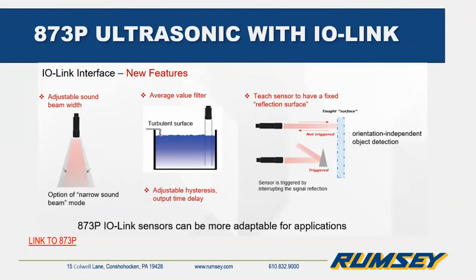Another problem with ultrasonics in fill detection or liquid level detection is a turbulent surface. With the adjustable hysteresis of the IO-Link, you can adjust out that turbulence. And then you can also teach the sensor a fixed reflective surface.